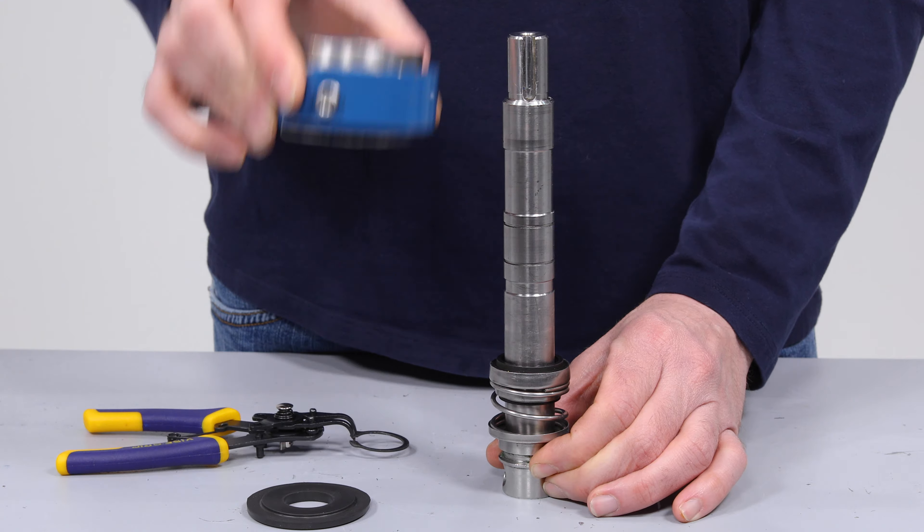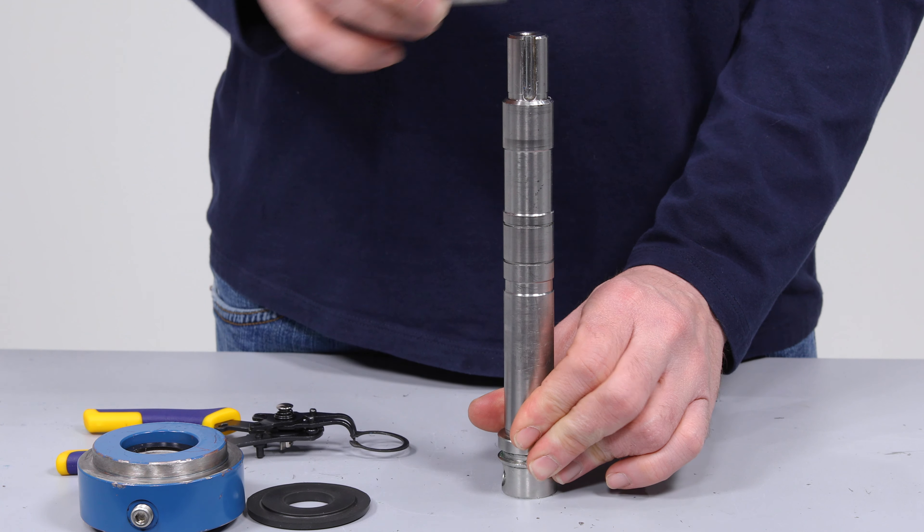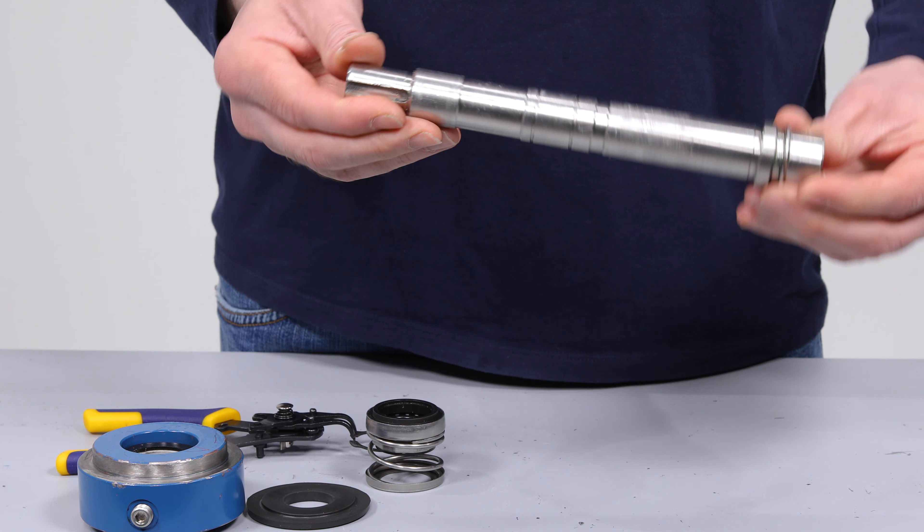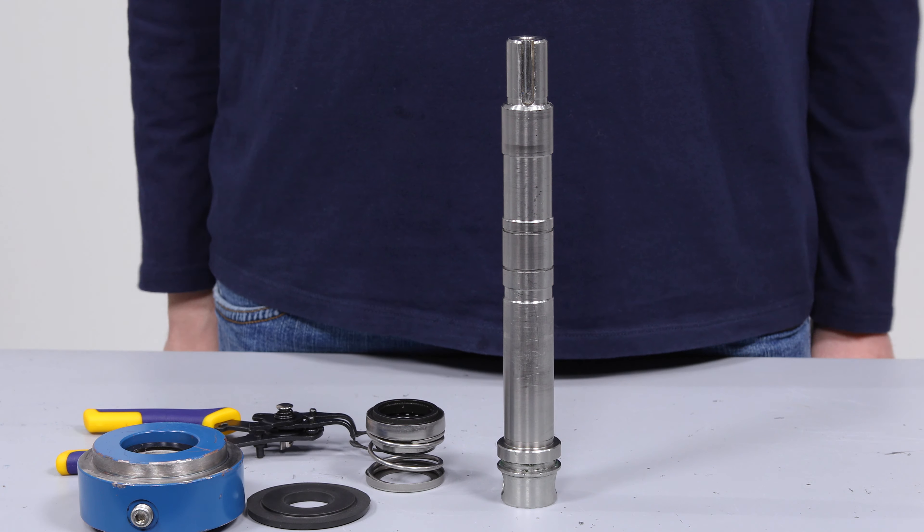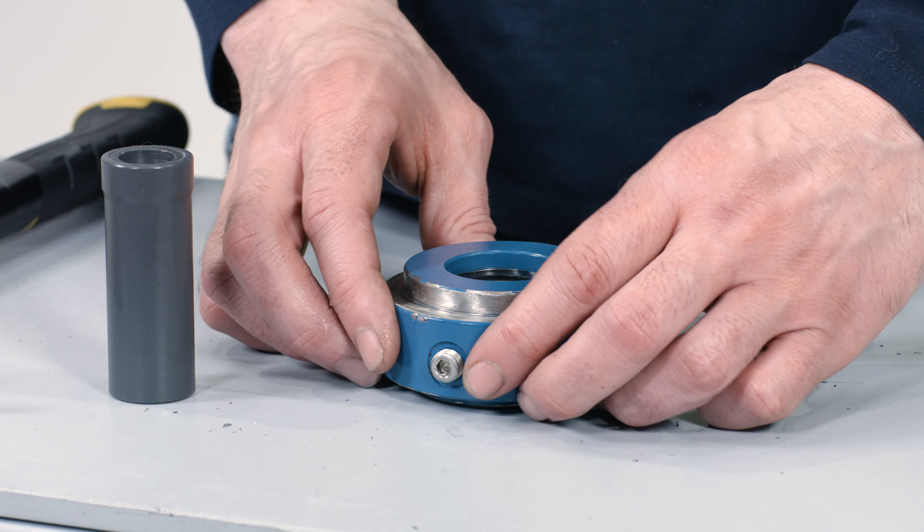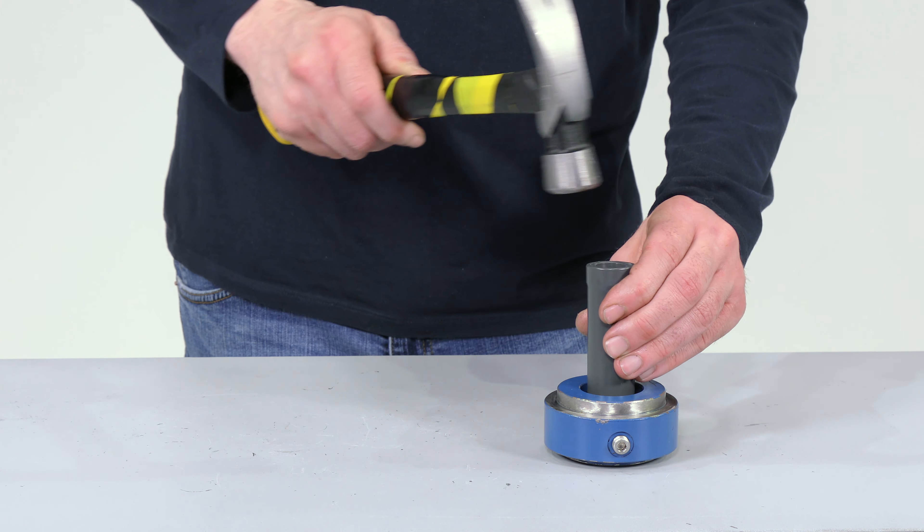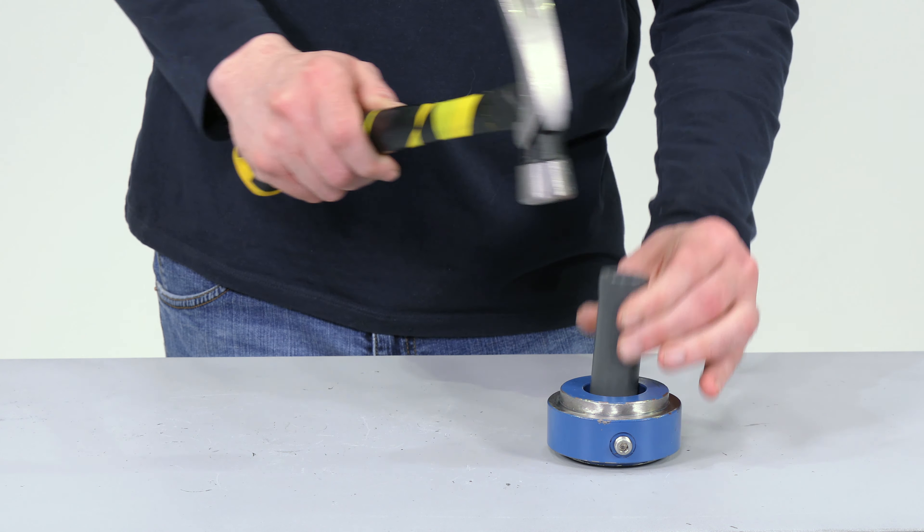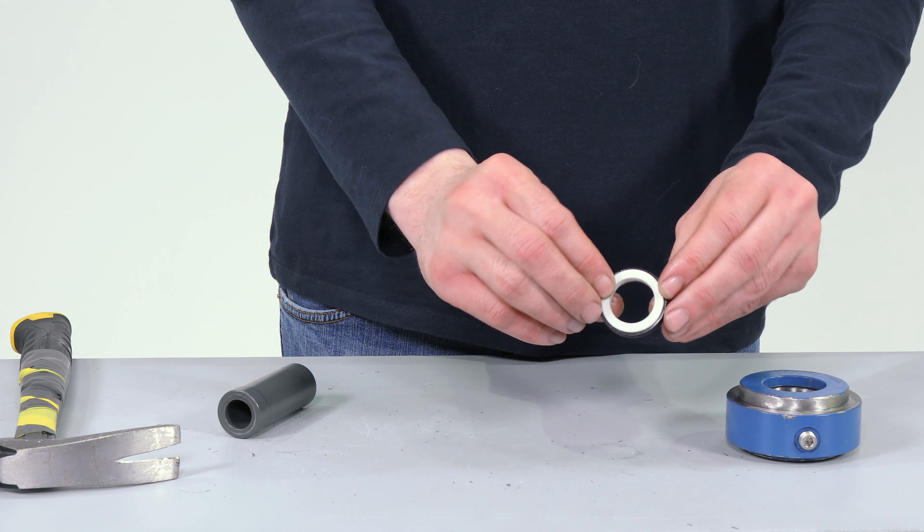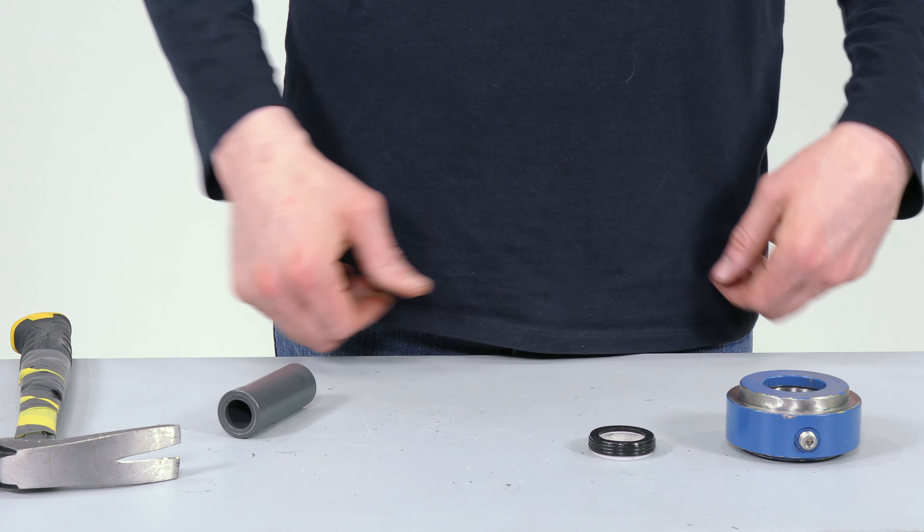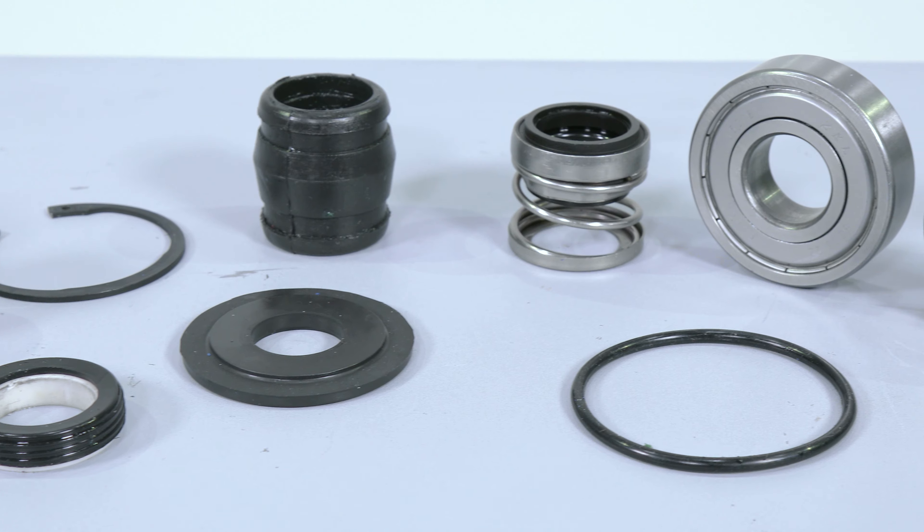Next, remove the seal housing. Remove the mechanical seal and spring. Use an adapter and hammer to remove the stationary face of the mechanical seal assembly from the seal housing. Make sure to inspect all parts for wear and replace if required.